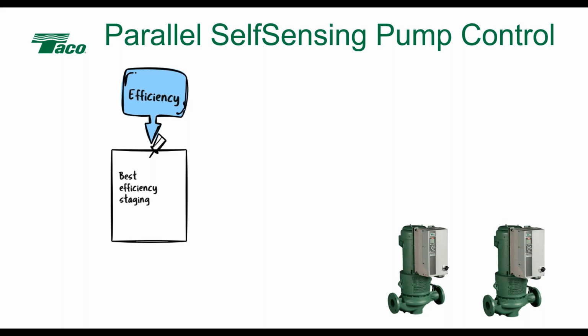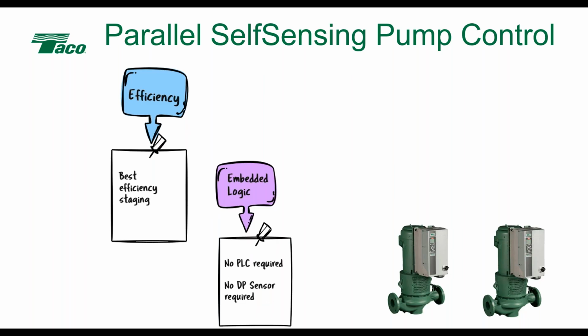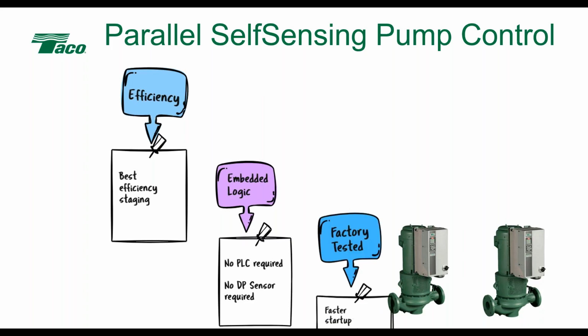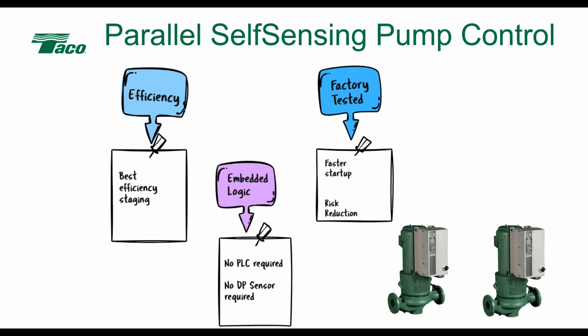10-4. So when we look at parallel self-sensing pump control, it's really about understanding efficiency and using best efficiency staging. It's about capitalizing on the embedded logic. You don't need a PLC, you don't need the DP sensor, you don't need the BAS guy to program anything, okay? You know, we're pump guys. We know this works. This is what we do every day. And it's been factory tested, which means that you're going to get faster startup and you're going to get lower risk. And who isn't more happy when they get lower risk, right?